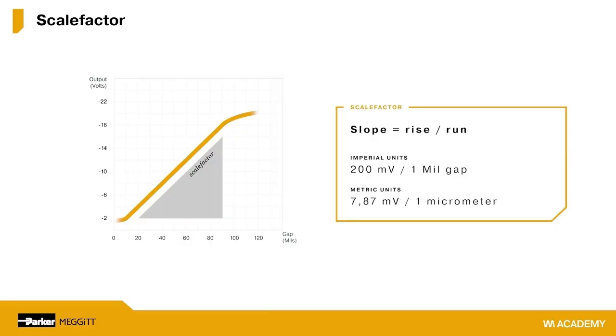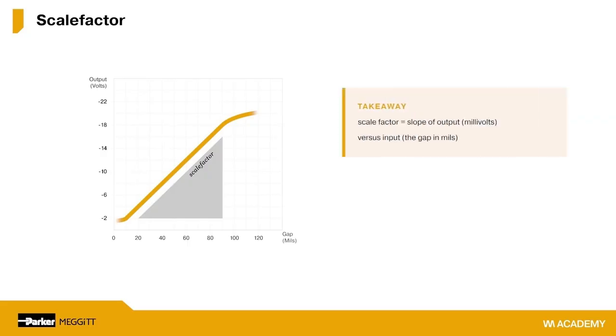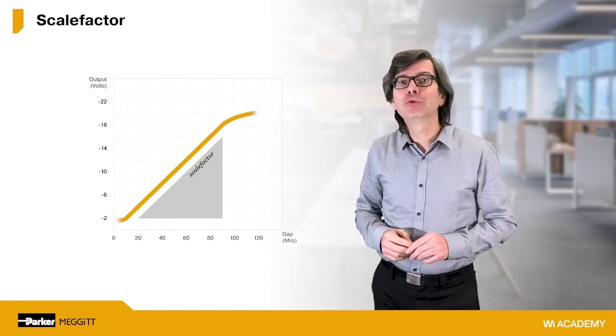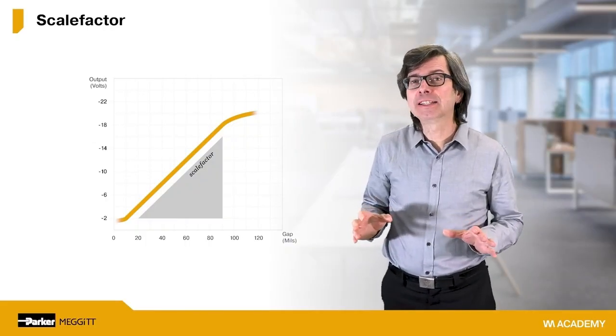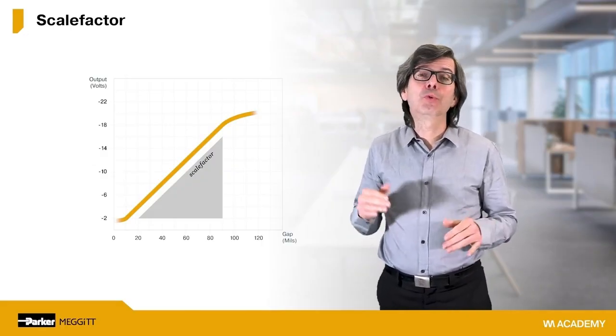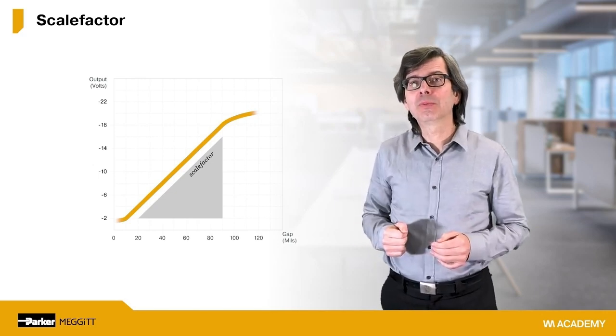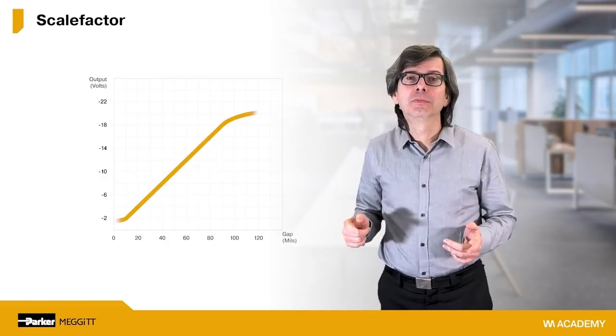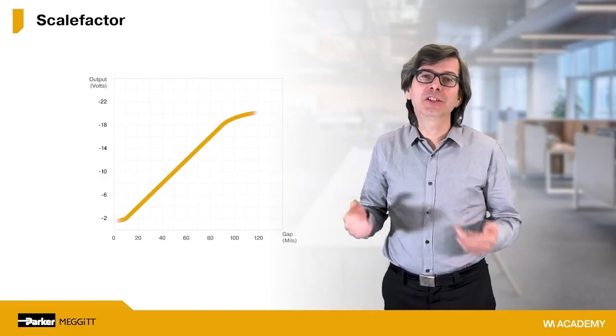You can think of this as the slope equals rise over run. The rise is 200 millivolt and the run is 1 mil. In other words, for every 1 mil change in the gap, the voltage changes by 200 millivolts. The important takeaway here is that the scale factor is simply the slope of output, millivolts, versus the input, the gap in mils. If we were to use the metric system and change our horizontal axis to micrometers, the scale factor would become 7.87 millivolts per micrometer. And now, let's use this concept to convert a changing gap to a changing voltage.